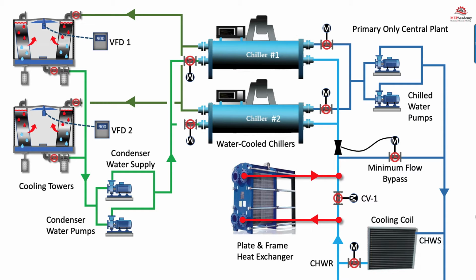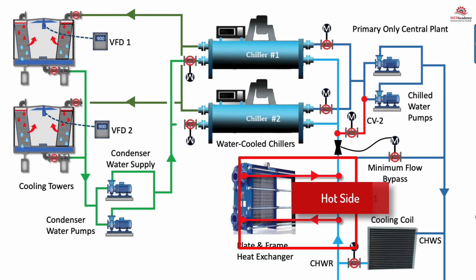When in full waterside economizer mode, we need to add a bypass line so that all the water avoids going through the chillers in order to save on pump energy. We'll add a control valve CV2 to open fully while both chiller control valves will be closed to prevent water from going through the evaporator coils. This completes one side of the heat exchanger, which is the hot side.